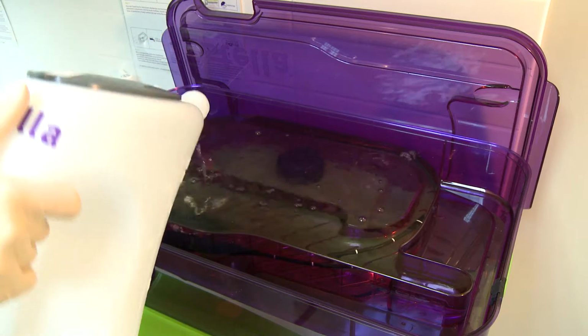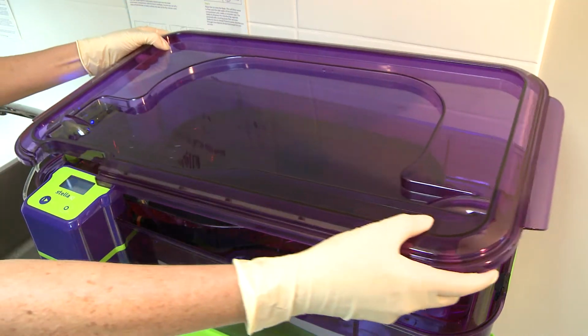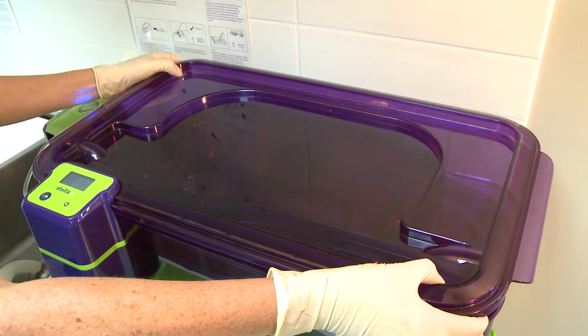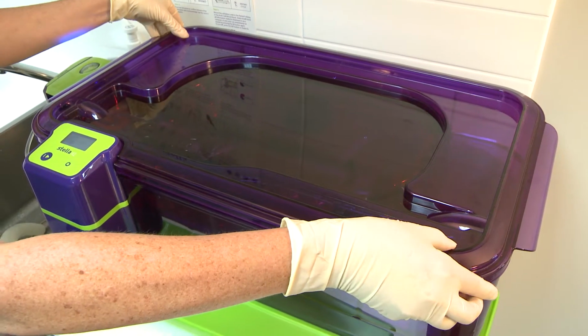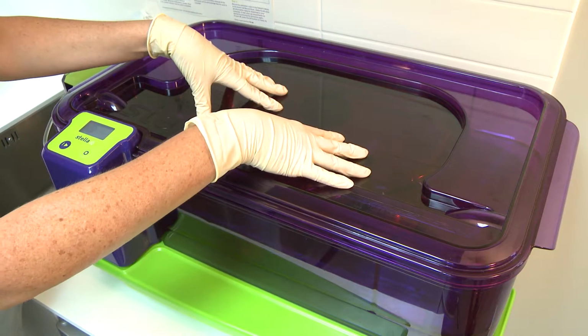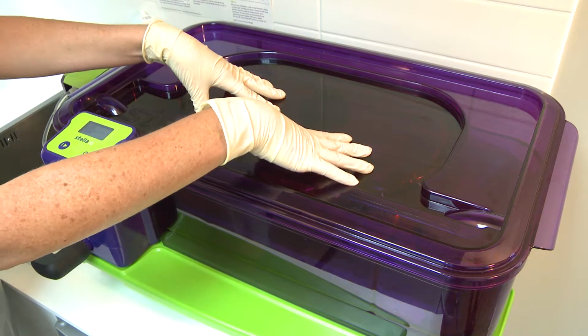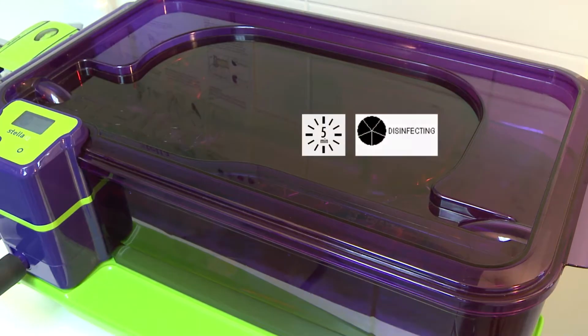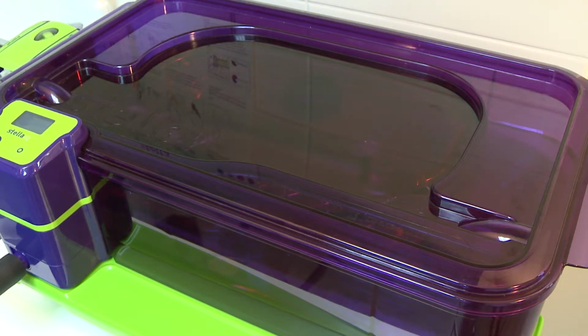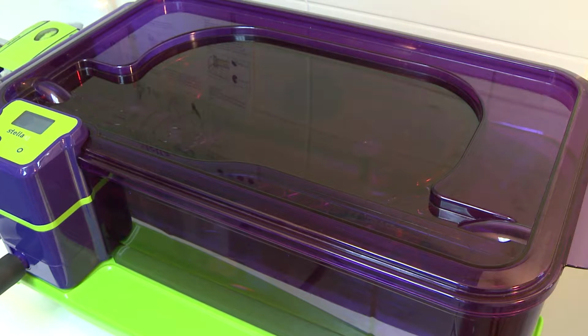A beep confirms the start of the 5-minute cycle. Place the lid on the base. This liquid will overflow over the side walls of the instrument compartment, creating a complete seal of disinfectant. Stella IQ displays the disinfecting wheel and will automatically count down 5 minutes. Stella IQ directs Stella Pulse to pump disinfectant through the channel of the instrument for 1 minute.